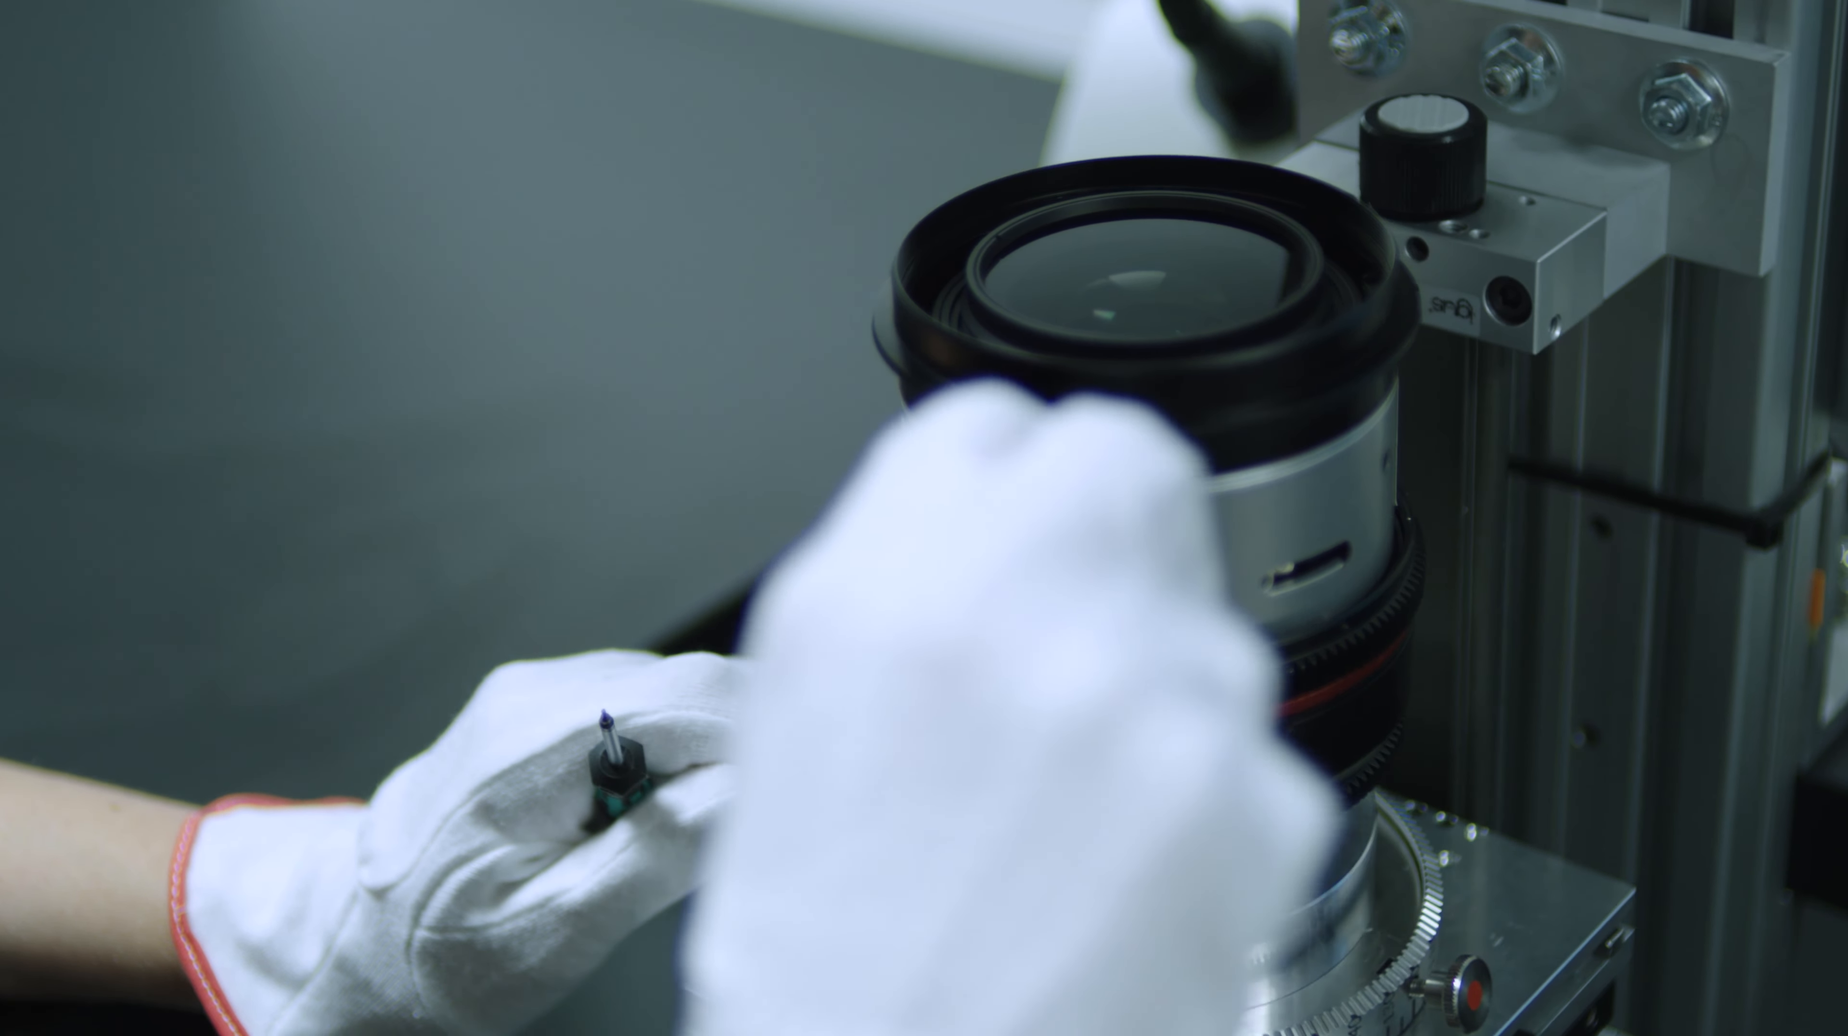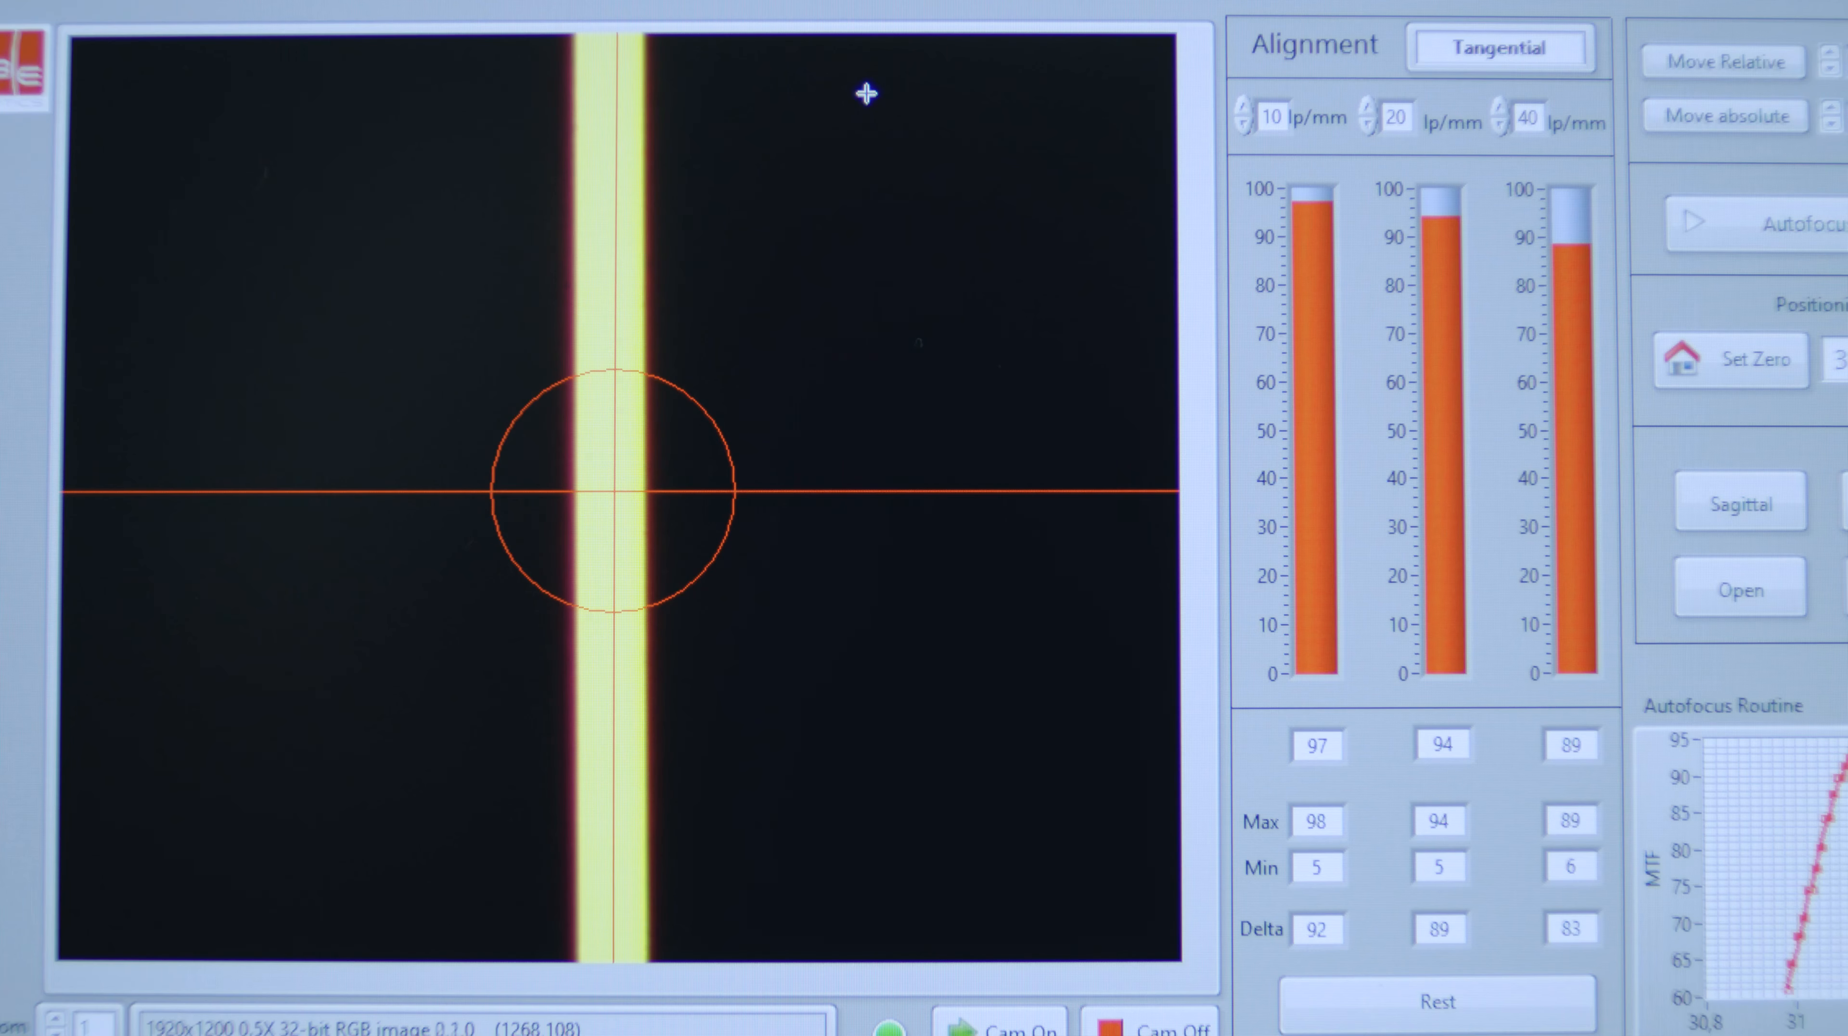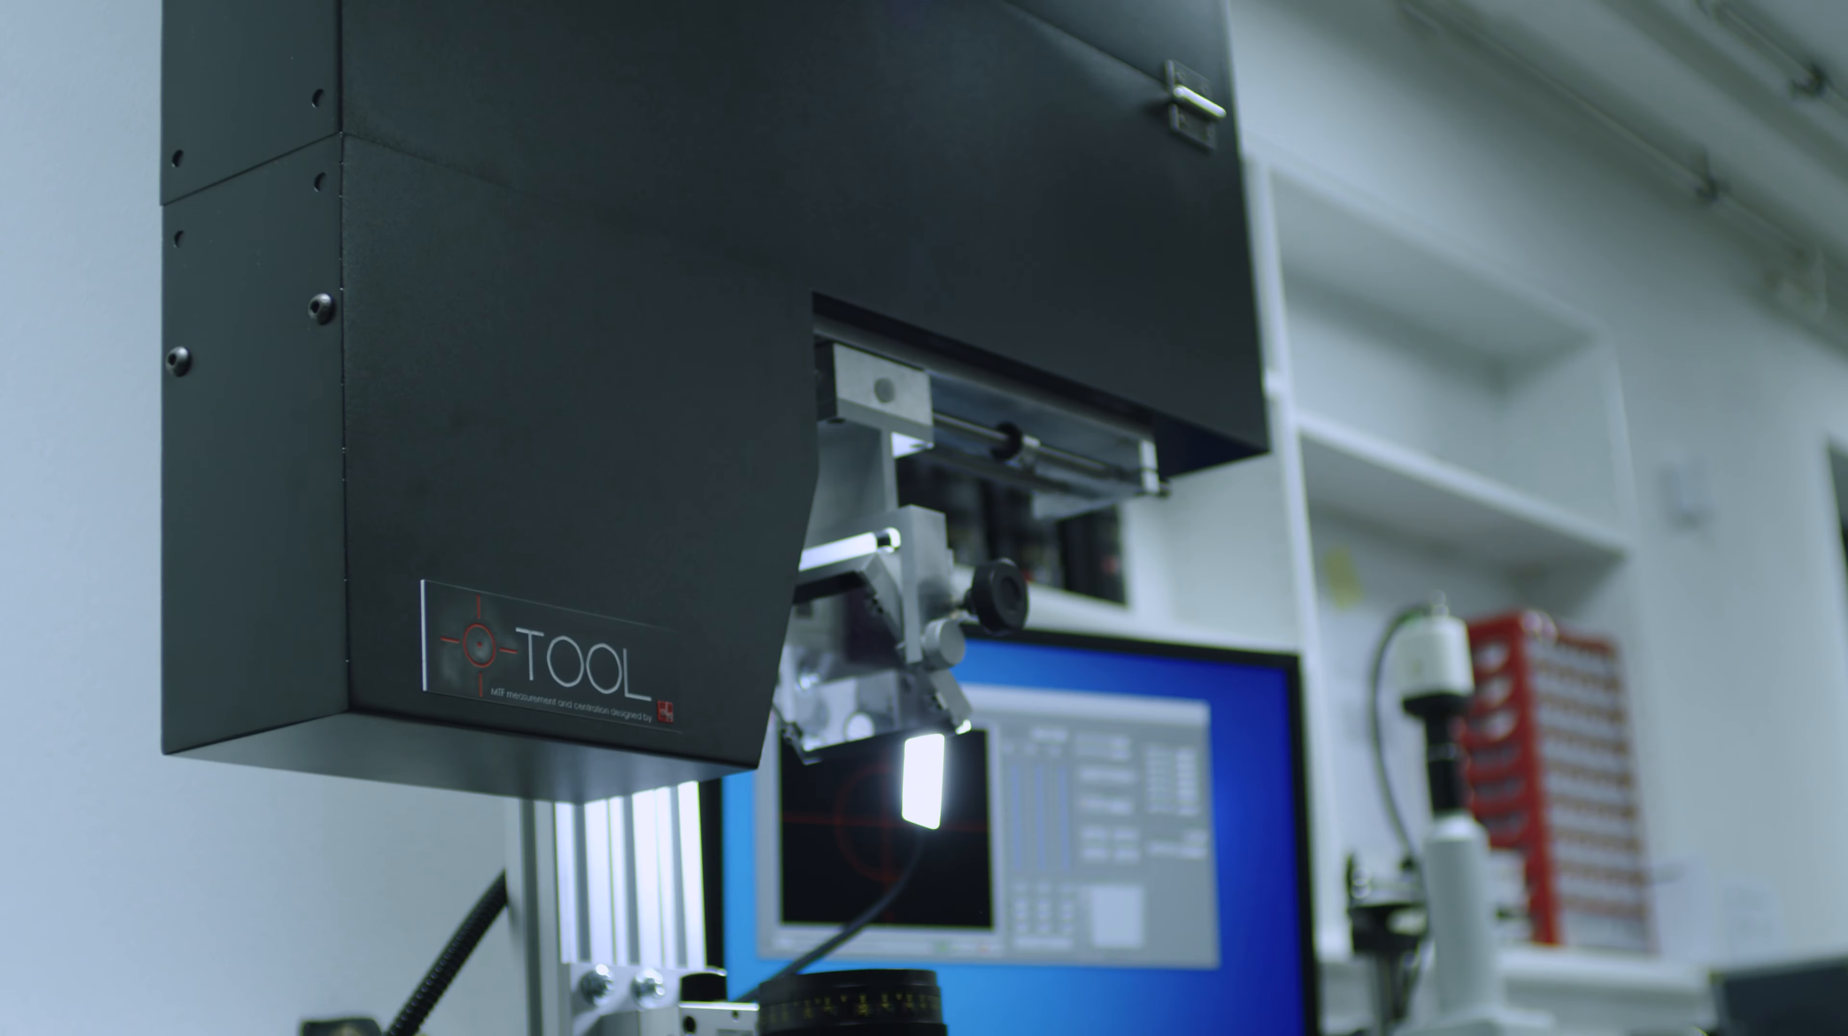MTF as a function of image height and as a function of back focal distance, motorized switching between tangential and sagittal slit alignment.